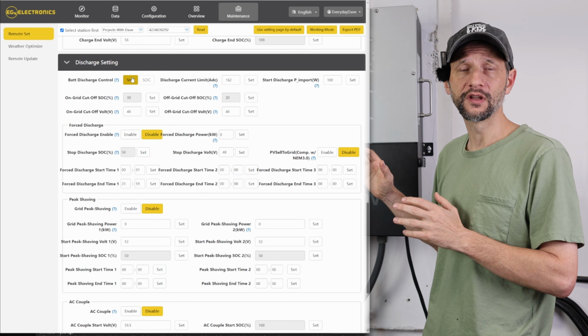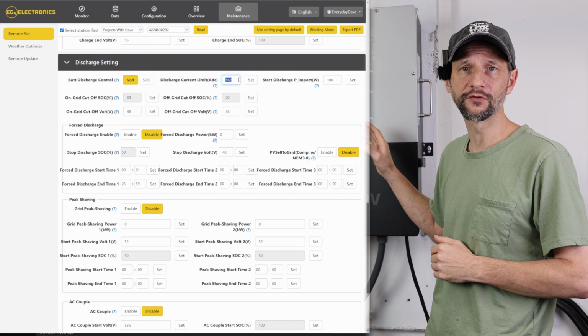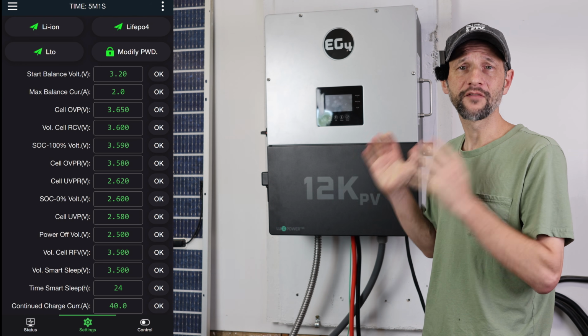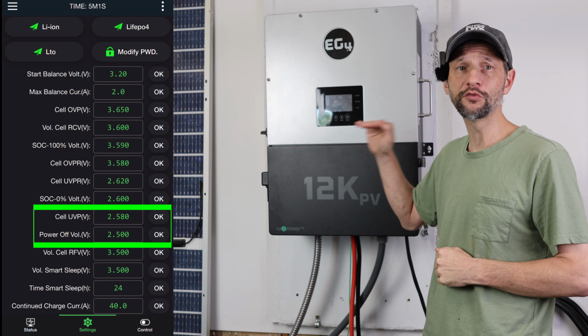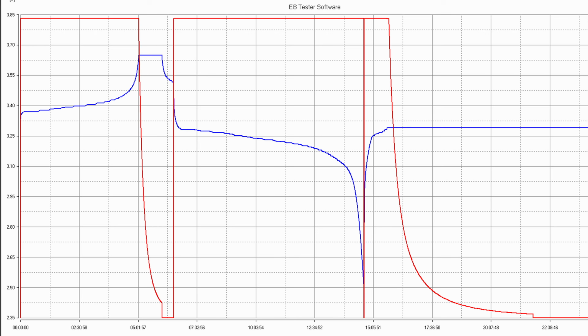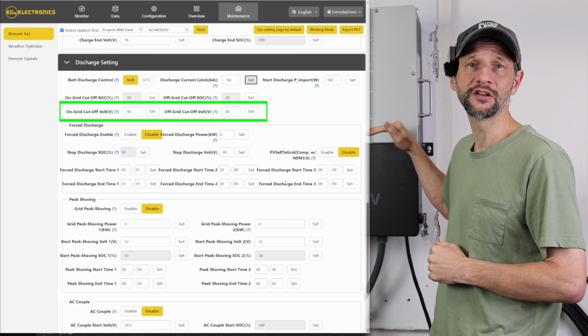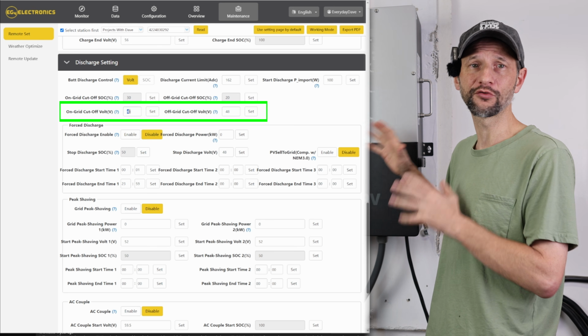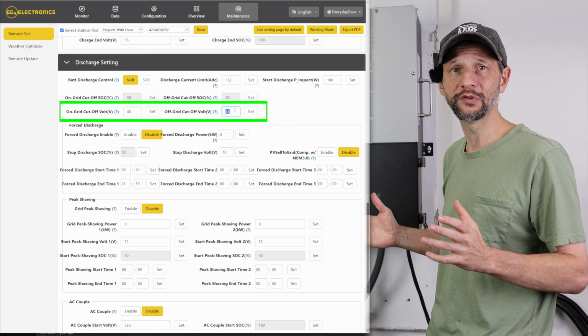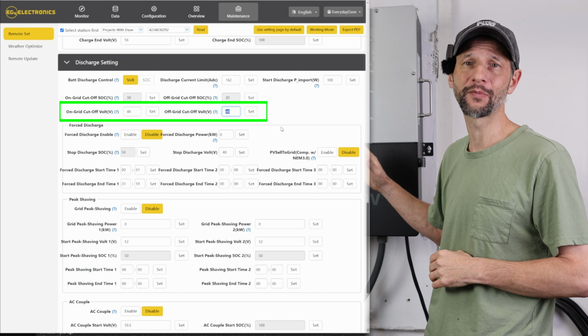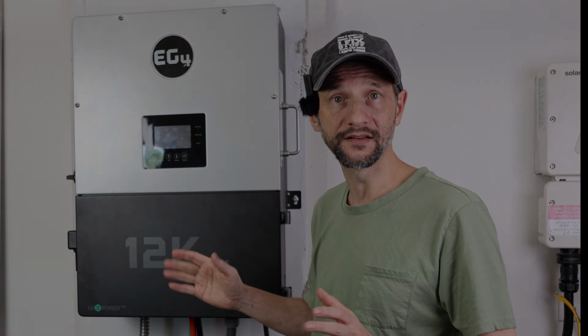I set the charge current limit to 162 amps for this inverter, and we'll use the end of discharge voltage from our chart. I have my BMS set to the minimum at 2.5 volts, but you can see there's no real capacity left past 3 volts, so I can set the pack at a minimum of 48 volts to reduce the stress on the battery, and I'll still be able to use at least 95% of the capacity. And that's all the settings.